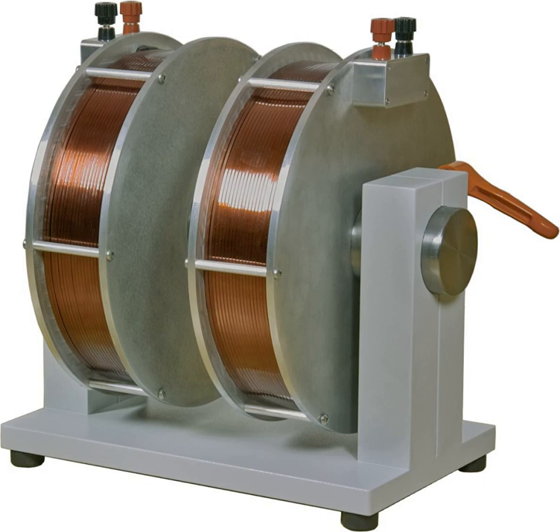Hysteresis losses: reversing the direction of magnetization of the magnetic domains in the core material each cycle causes energy loss, because of the coercivity of the material. These losses are called hysteresis. The energy lost per cycle is proportional to the area of the hysteresis loop in the BH graph. To minimize this loss, magnetic cores used in transformers and other AC electromagnets are made of soft, low coercivity materials, such as silicon steel or soft ferrite. The energy loss per cycle of the AC current is constant for each of these processes, so the power loss increases linearly with frequency.